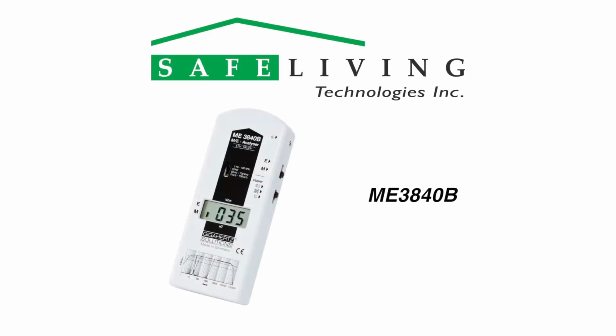The ME3840B is an easy-to-operate, low-frequency broadband EMF meter that measures AC electric and AC magnetic fields. It can also be referred to as an AC electric field meter, Tesla meter, or Gauss meter. This meter is designed to measure the invisible pollutants that radiate from electrical wiring and devices that use AC power.